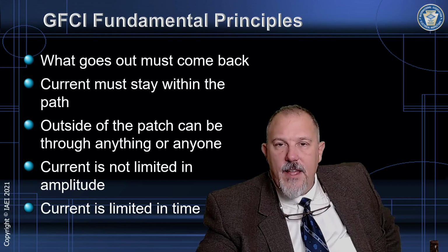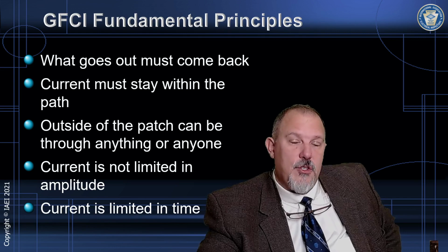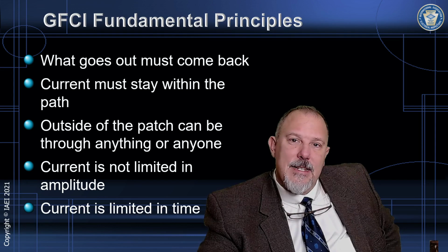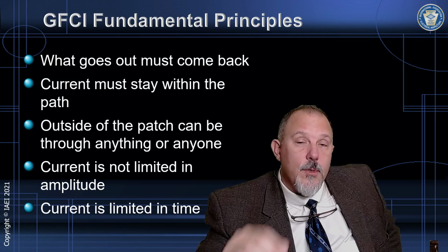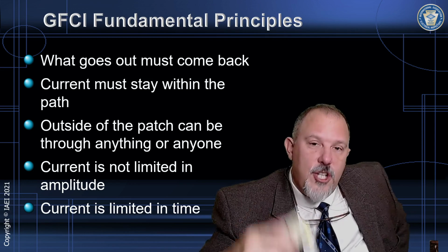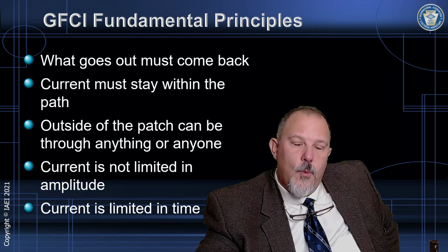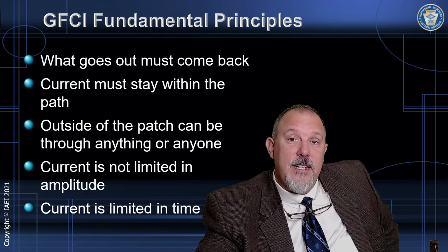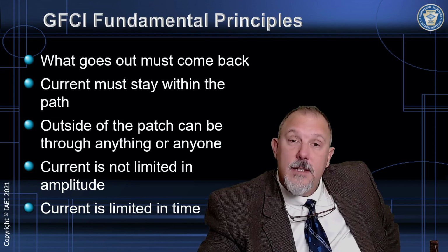If I calculate 5 amps will pass through your body, when you're on a GFCI, 5 amps will still pass through your body. It will trigger at 4 to 6 milliamps, but it doesn't limit the current that flows to only 4 to 6 milliamps. You will still see 5 amps worth of current passing through your body. The GFCI device or circuit breaker will limit the amount of time so that your healthy heart won't go into fibrillation. That's how a GFCI will work to save a life.